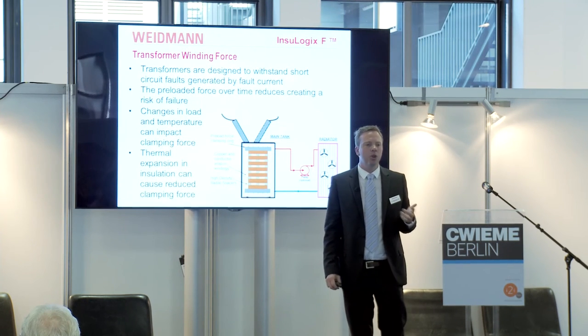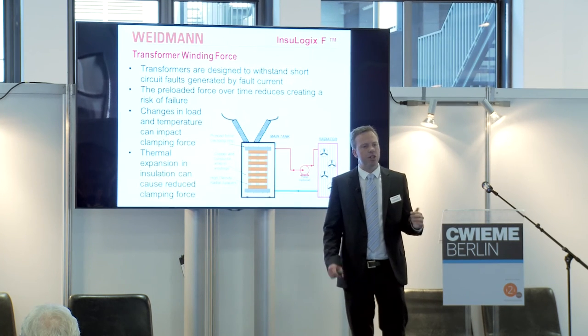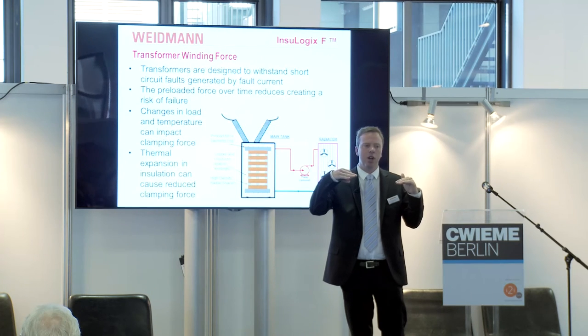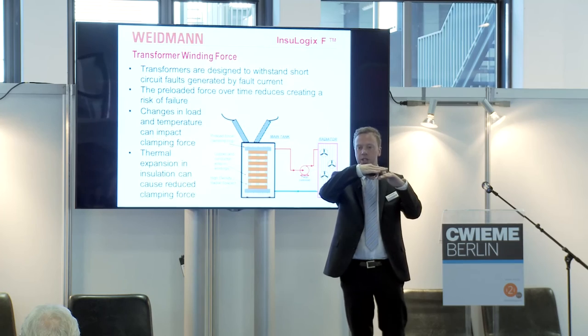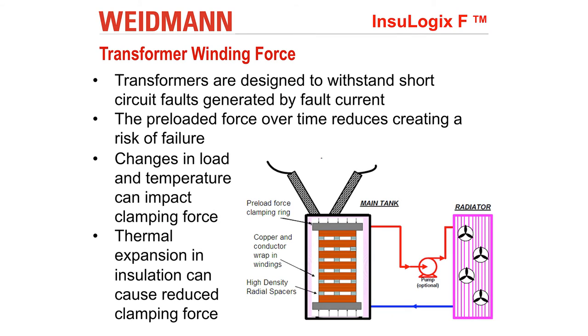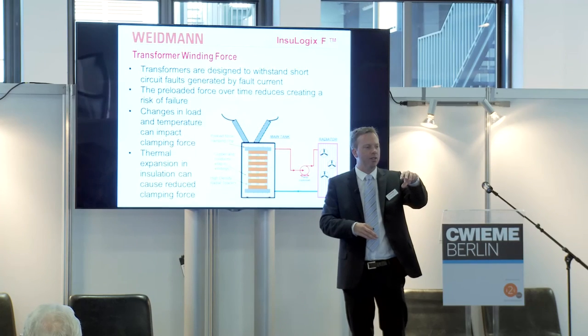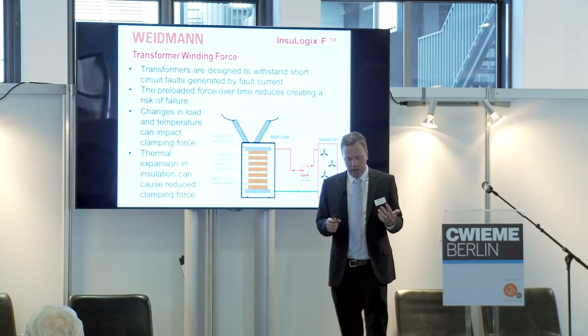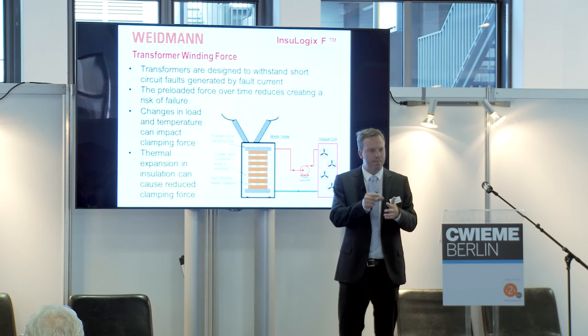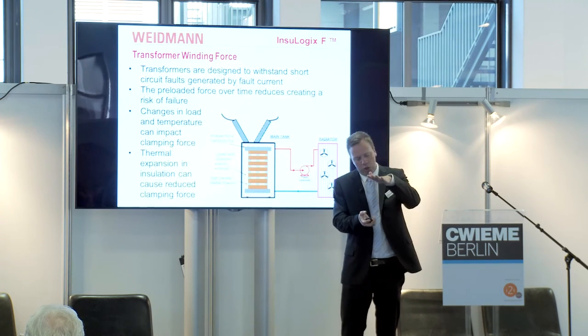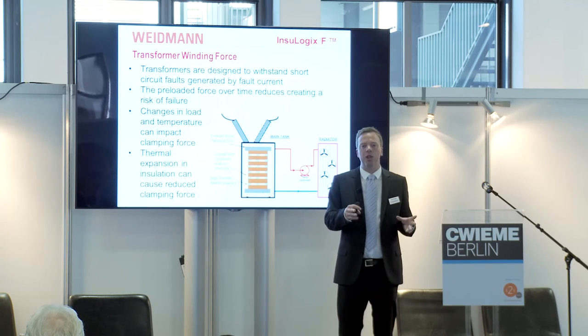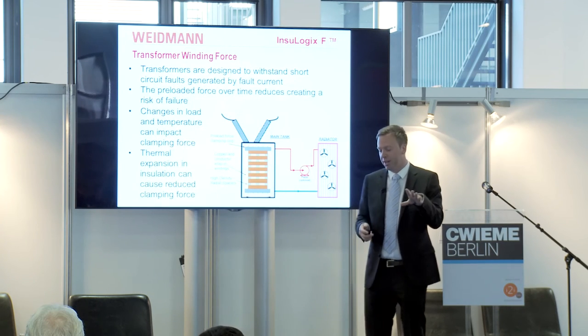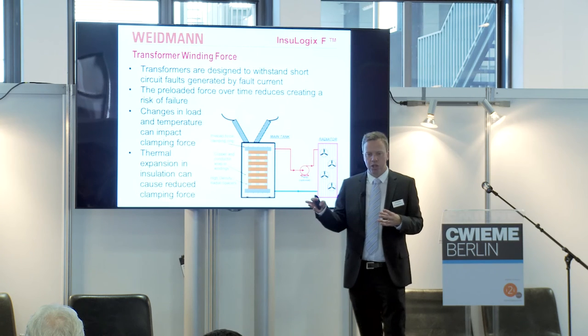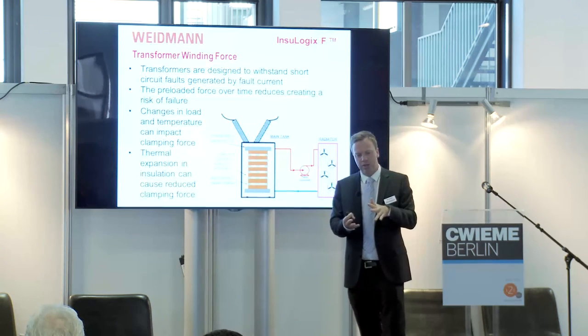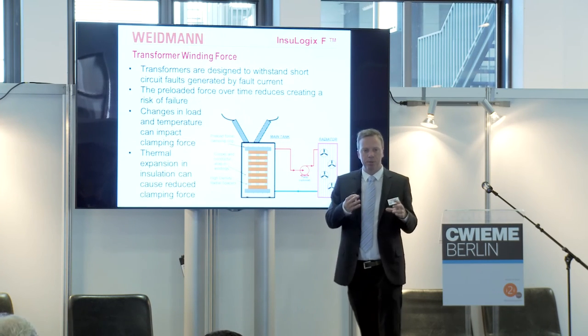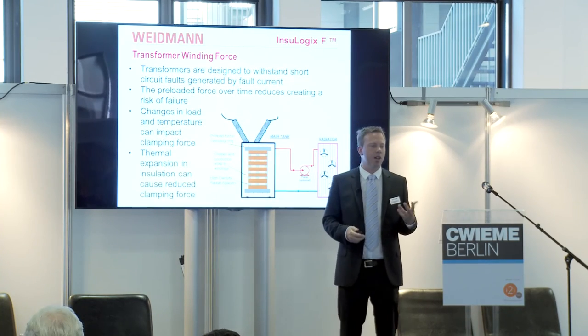If we're only in the key spacers in the transformer itself, we'd miss the key information, which is the swelling and decreasing of the insulation and changes within the transformer, not necessarily the bolting mechanism of the clamping ring. So we use key spacers with a fiber optic monitor embedded in them. We have a patent on that to look at the pressure on each individual winding, so we can tell you if there's any change in clamping force on that particular winding. There are a number of contributing areas, like temperature and load, which contribute to thermal expansion. All of these parameters within the transformer, temperature, moisture, and force, can be collected and delivered.